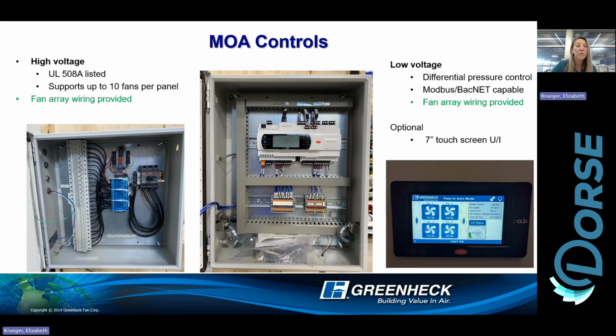So the touch screen is useful. It'll keep track of if maybe one of the fans goes down, or if you wanted to modulate a different set point. We do have Sure Air built in to all of these fans. A lot of times they'll just put a certain set point for CFM or static that they want to keep the system pressure set to. Otherwise, if you do have a BMS, it will integrate with Modbus BACnet capable as well.